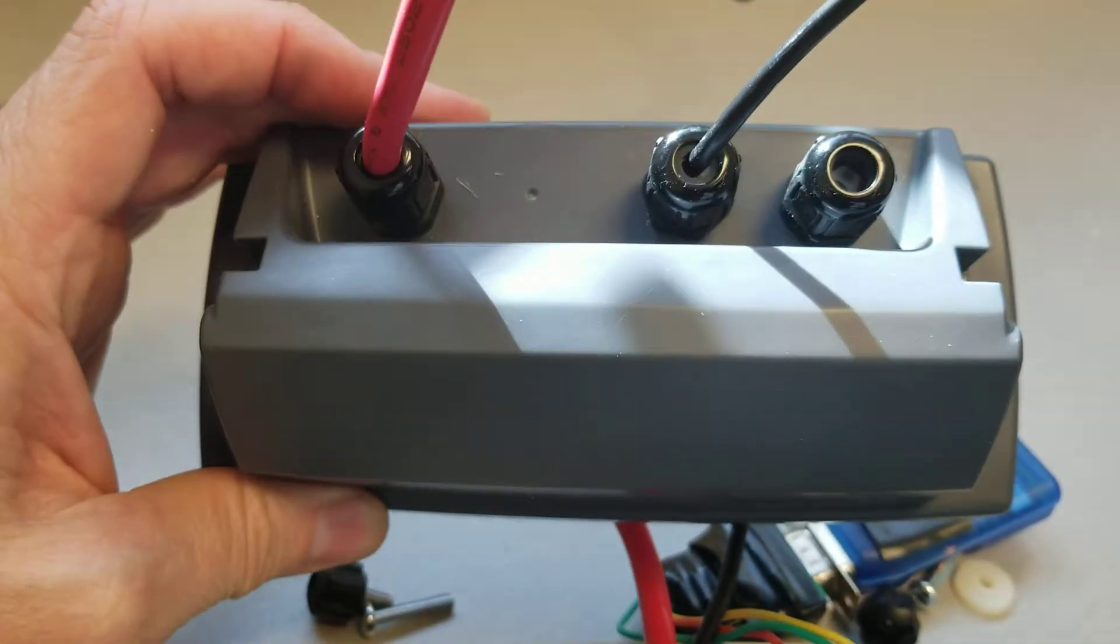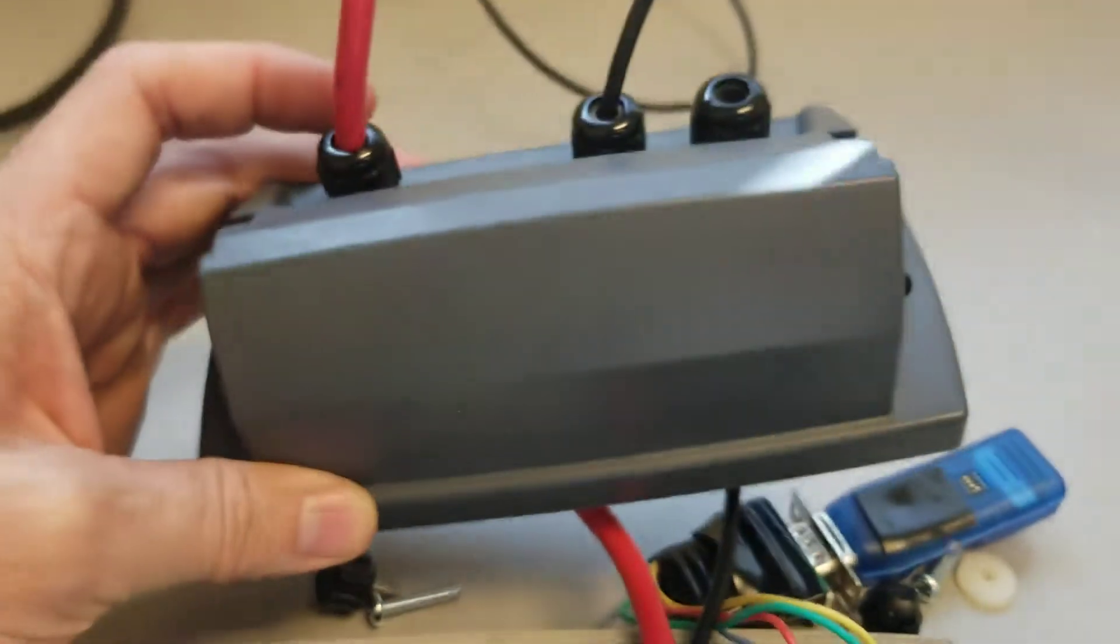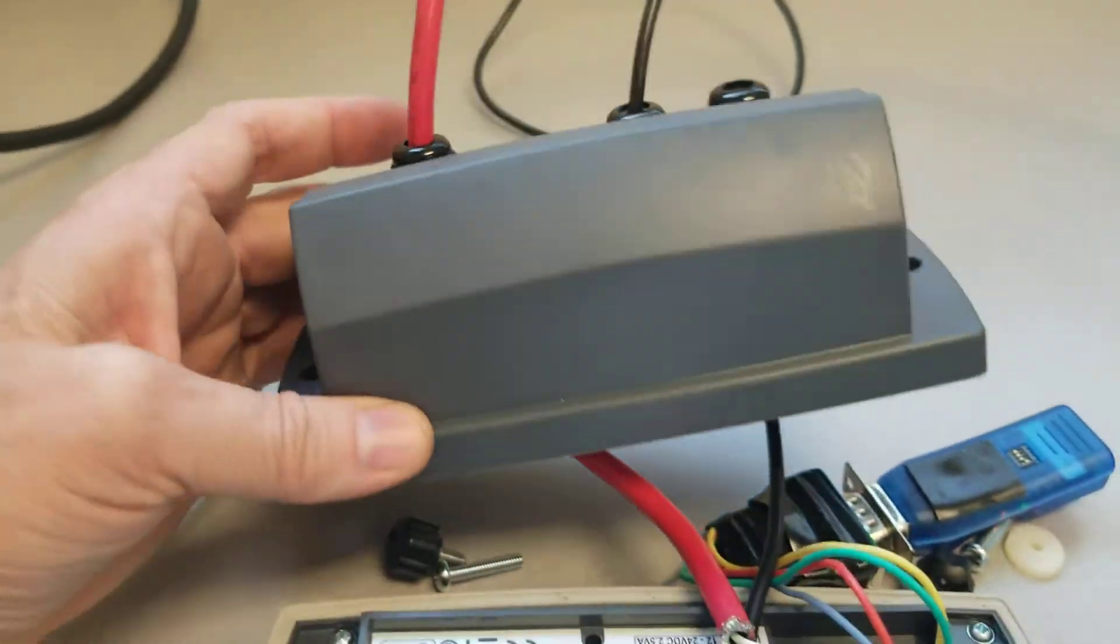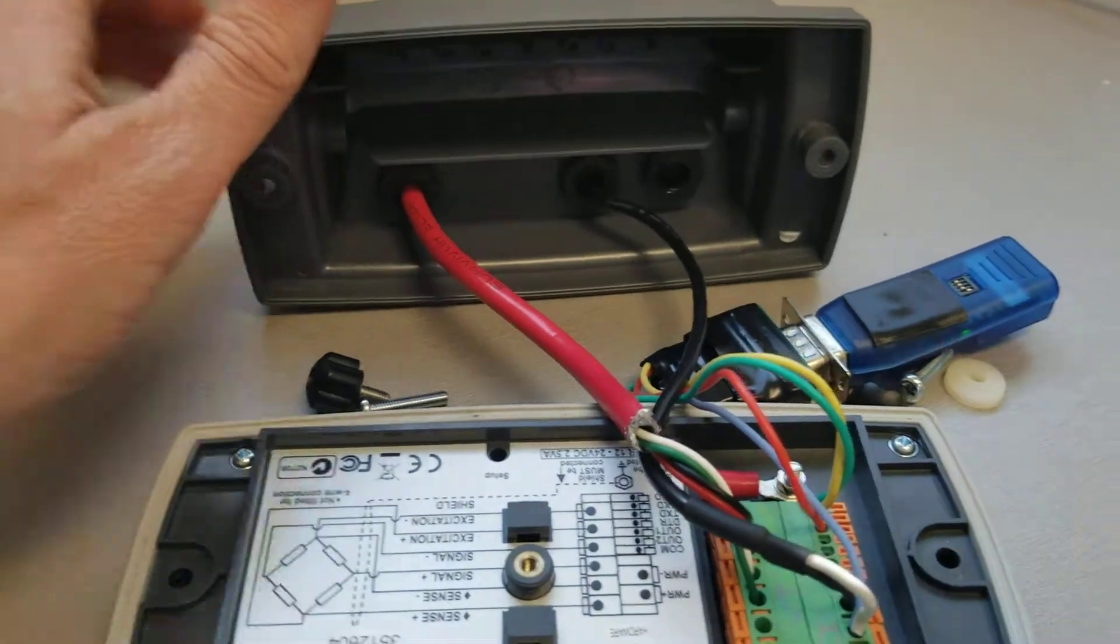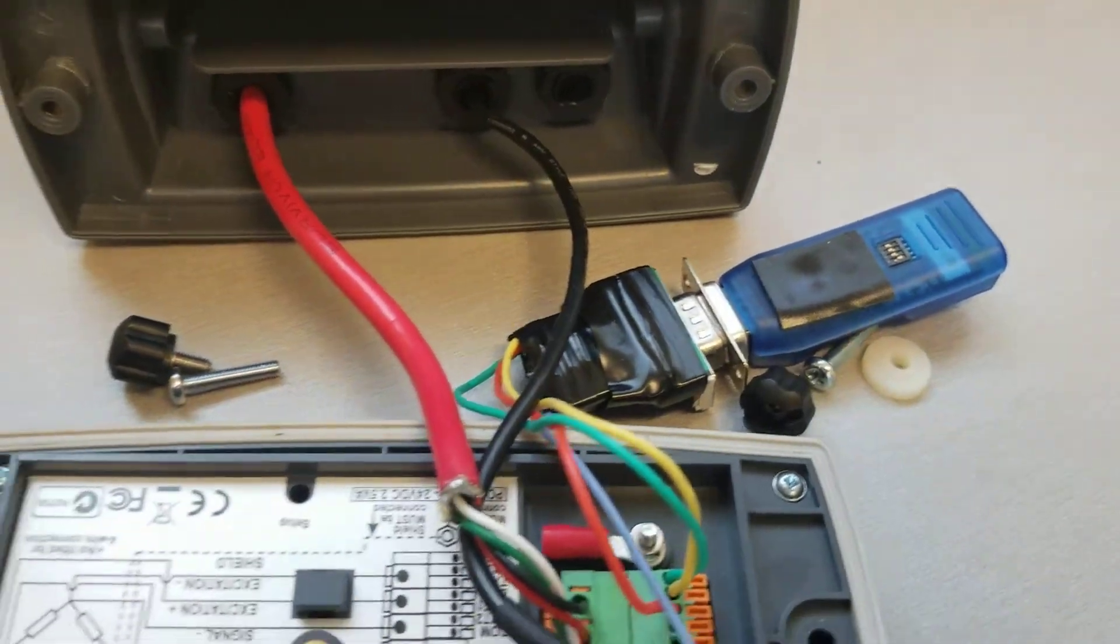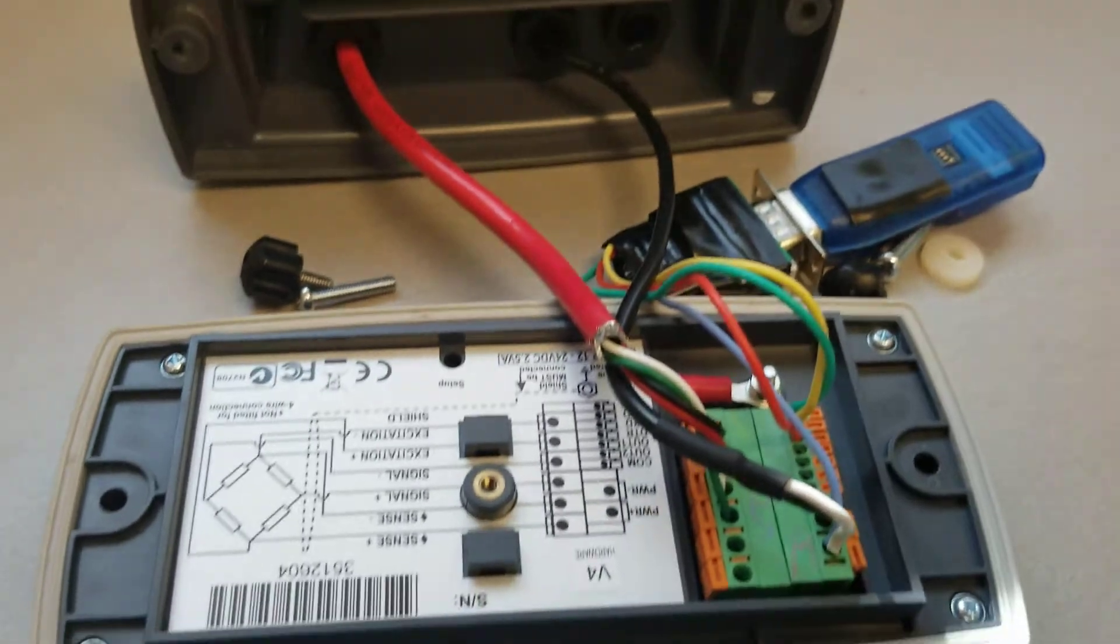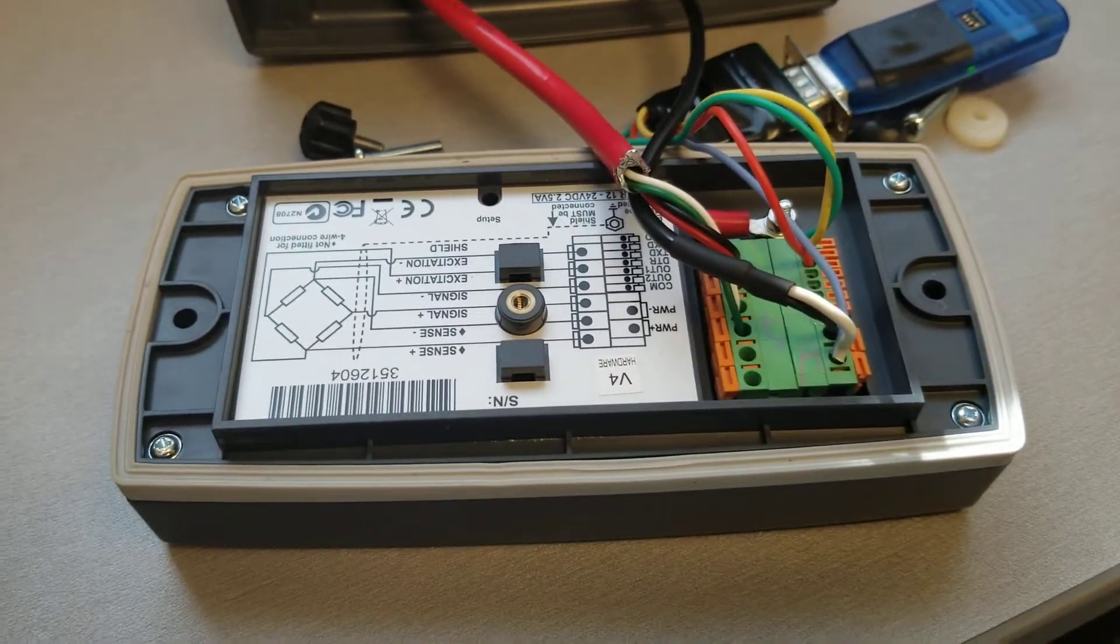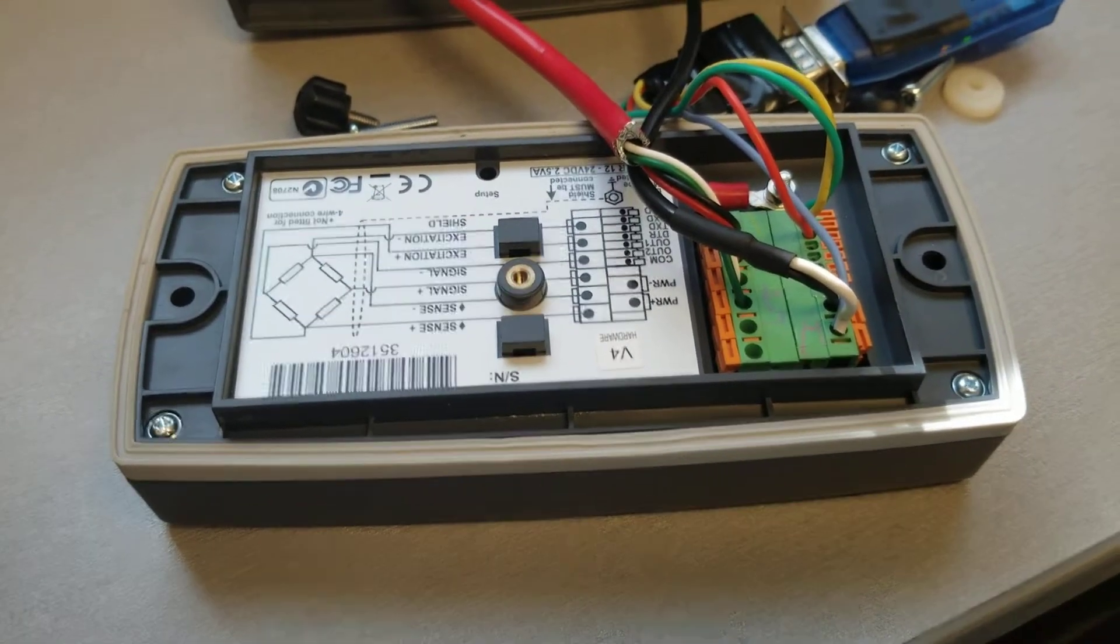The red cable is the load cell. Black cable is the power. If you notice there's no communication cable. That's because in this case we're communicating with Bluetooth. That's a little Bluetooth dongle. That blue thing there it's blinking. That allows us to communicate to whatever device we want to over Bluetooth.